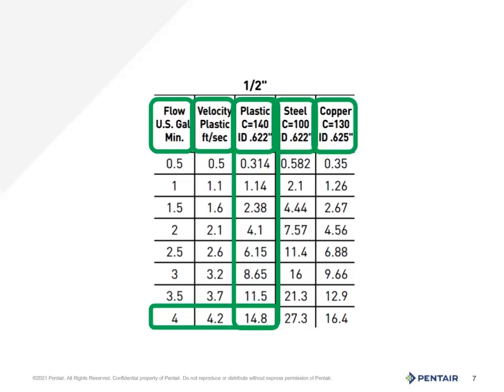So how do we read the chart? It's very straightforward. First, find the diameter of the pipe in question — here we're looking at half inch. Second, what is the design or desired flow for that pipe in the system? In this case, we're looking at four gallons per minute. And finally, what is the material of construction that we're flowing through? As you see here, we've highlighted four gallons per minute. The next two columns will show velocity in feet per second, and here we have a velocity of 4.2 feet.